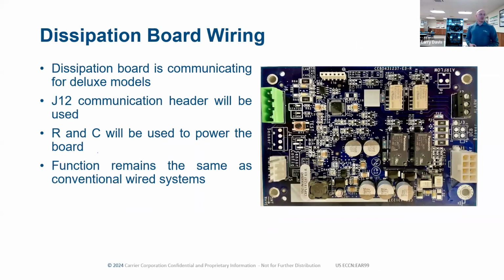Question is, is this a board in addition to the blower control board? Yeah, it's a totally separate board. If you're using it on a communicating system, and you'll see it in the wiring schematic, we don't use, on our communicating systems, typically like when you're powering up your wall control, you're using C and D for your 24 volts for the wall control. We don't use that on the dissipation board, where you'll still wire R and C to the dissipation board.